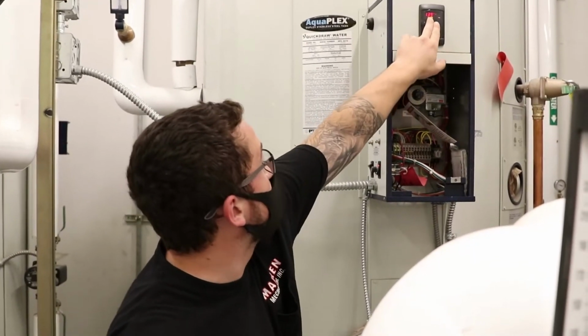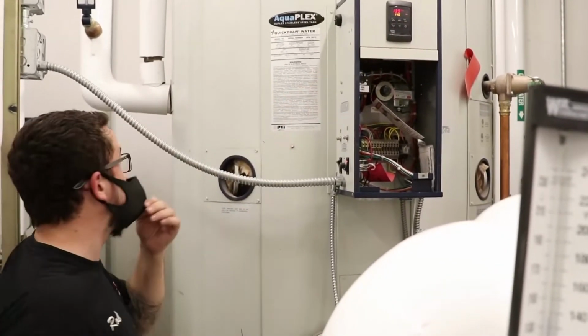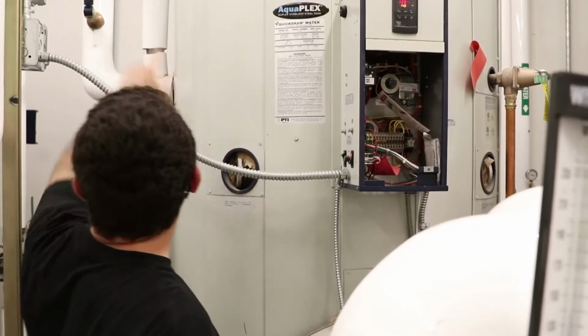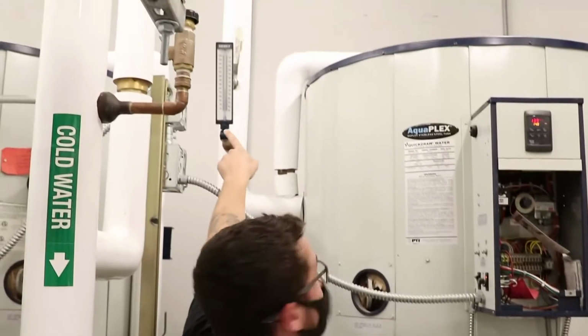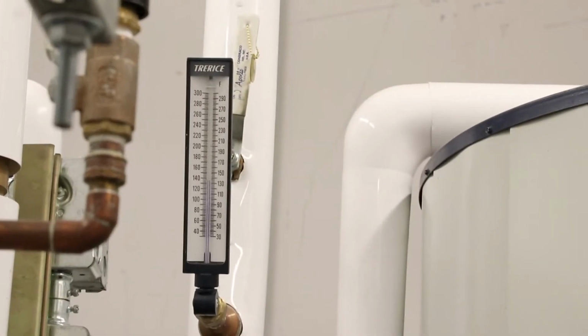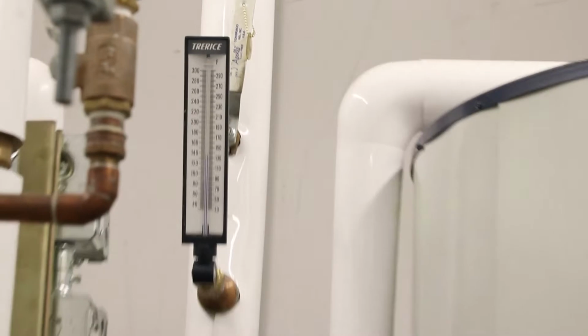This number right here, 139, is telling us the temperature of water that's currently leaving the tank. And if you look at that temperature gauge on the pipe, they match up perfectly. That's one way to cross-check these things and make sure that they're accurate and that they're giving you good information.